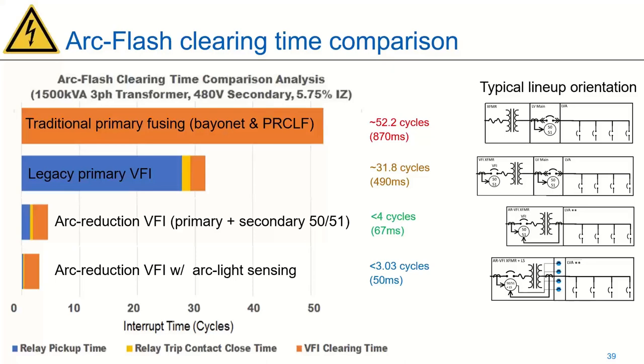Lionel is restating and wants to make sure that he's got it right. Basically, what has been done is introducing a vacuum interrupter inside the tank, triggered by the relay, so the fault clearing is taken away from the upstream fuse. Is that accurate? Essentially, yes.